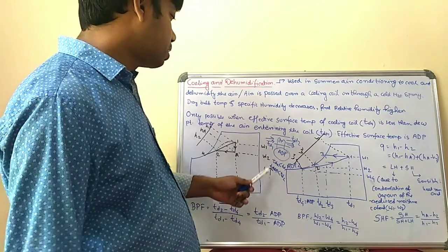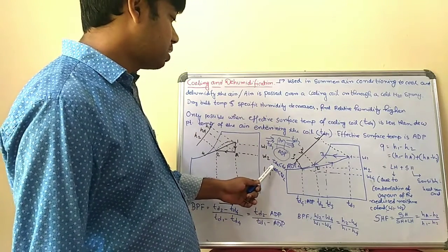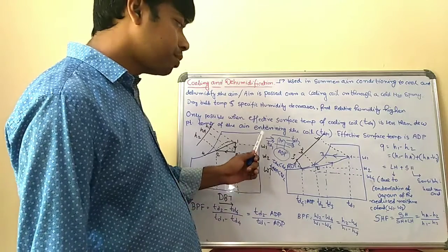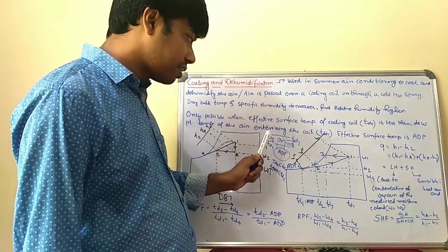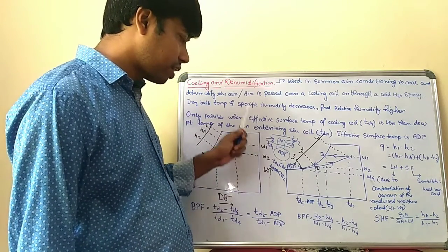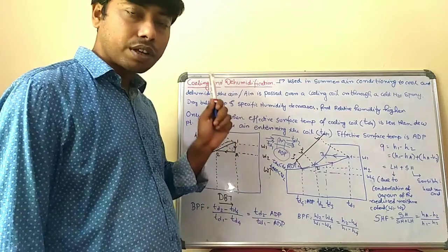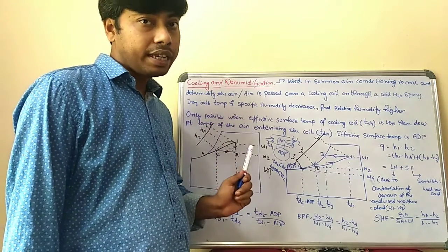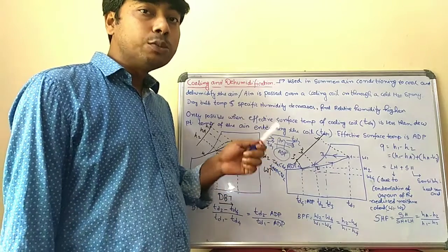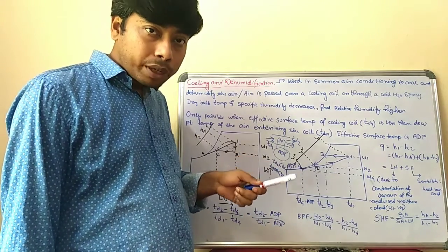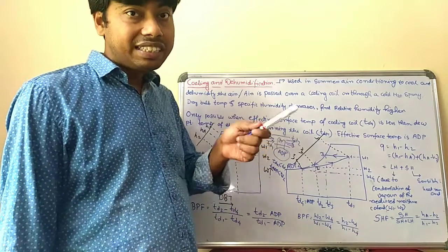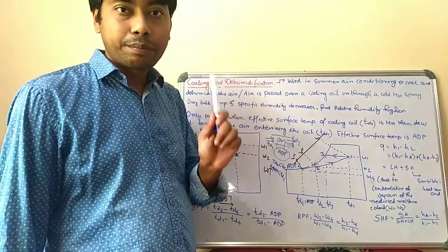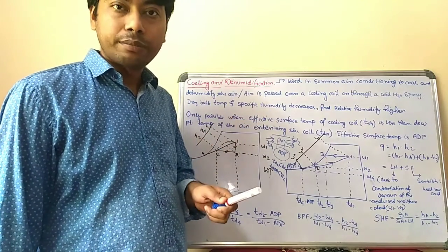First of all, you have to reach the condition TADP less than Tdp. When the air enters the duct system, you first have to know the dew point temperature of the entering air. Then you have to select the cooling coil temperature, which is less than the entering air's dew point temperature.